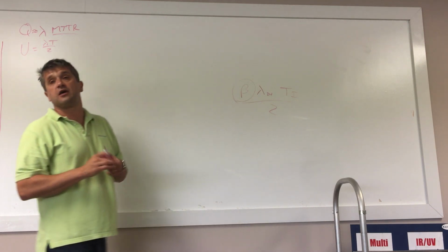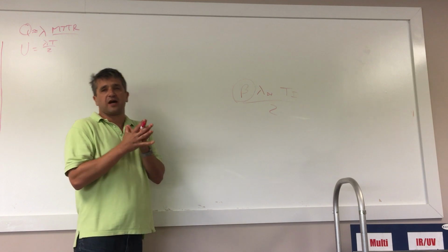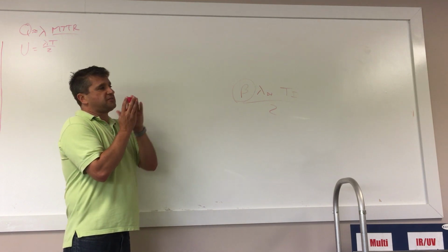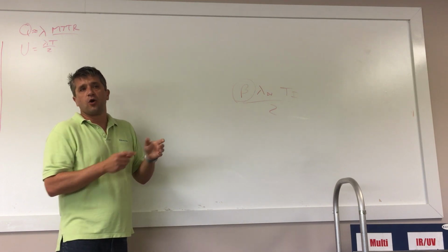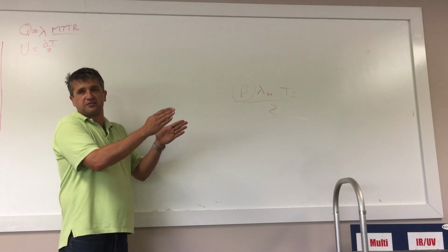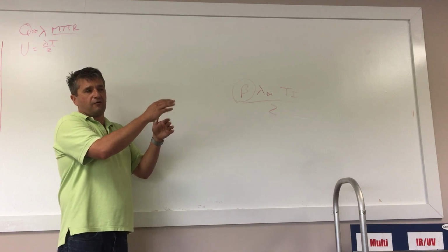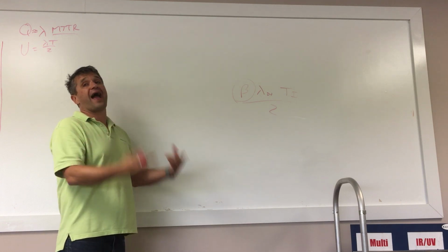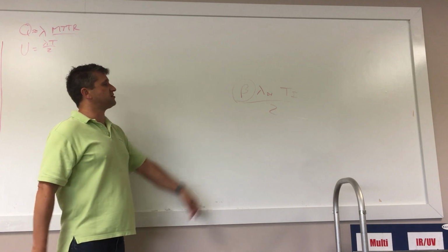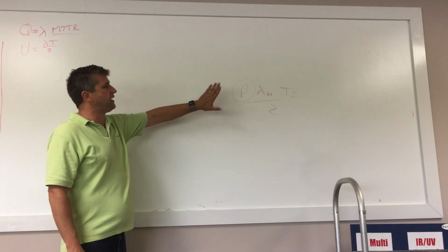So beta is the common cause factor, or the fraction of the time that a single stressor will cause all of the multiple components in a redundant voting arrangement to fail at the same time for the same reason.